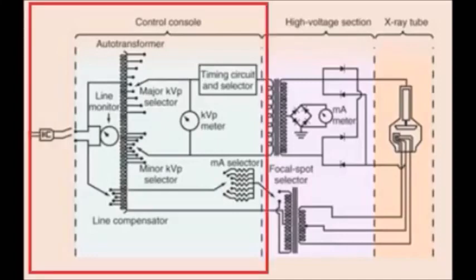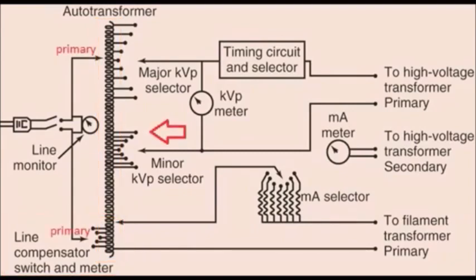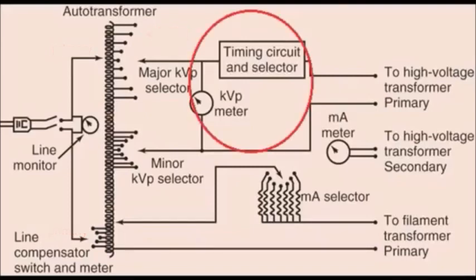On the left here we have the control console section. Main power is maintained at 220 volts by the line compensator and goes to the auto transformer where the major and minor kVp are selected through self-induction. There are tabs on the secondary side of this auto transformer — voltage is reduced by using the ones near the middle and increased by using the tabs on the outer ends. Power coming from the secondary side of the auto transformer then passes through the kVp meter and timing circuit, which control the length of the exposure.